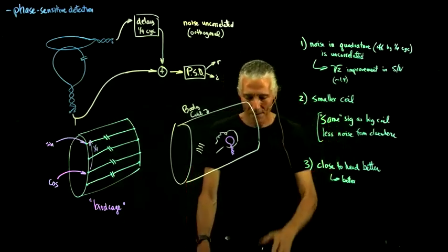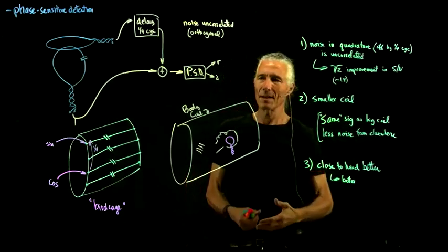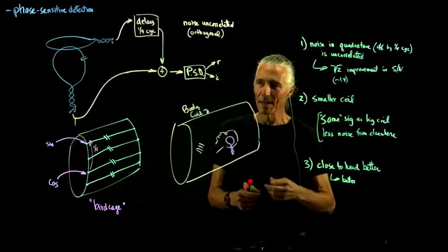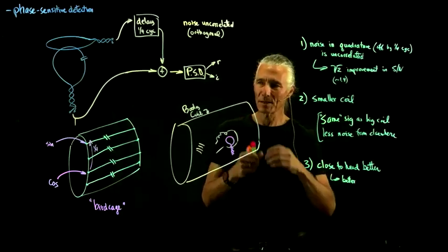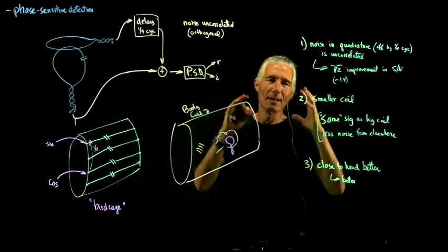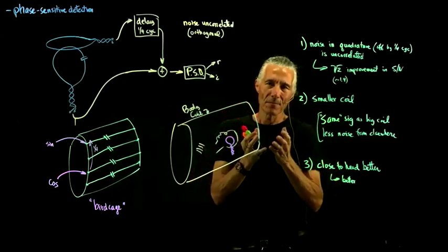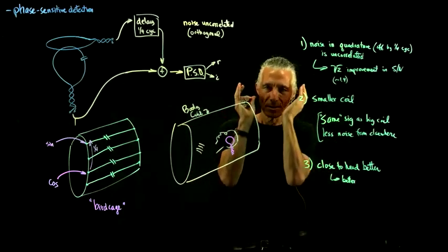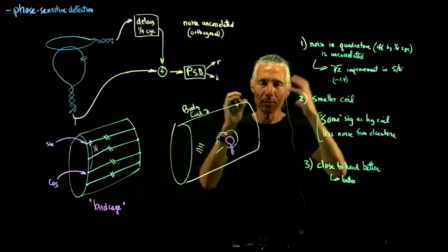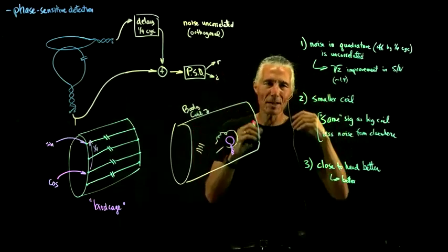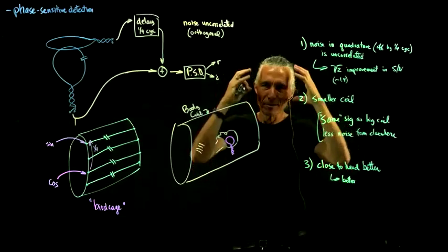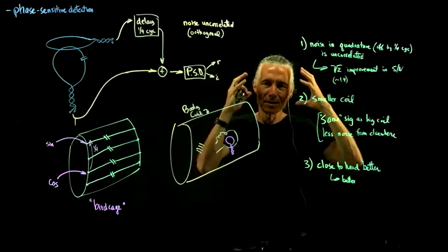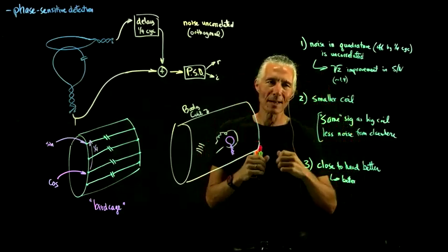So from the point of view of MRI technology, there's still at least a doubling of signal available if somebody could figure out a way to make a head coil that had a bunch of small coils that would be adaptable. The problem is people's heads are all different shapes, and so what they do is they make a hard head coil that will fit 2 standard deviations beyond the average maximum dimensions of a head.